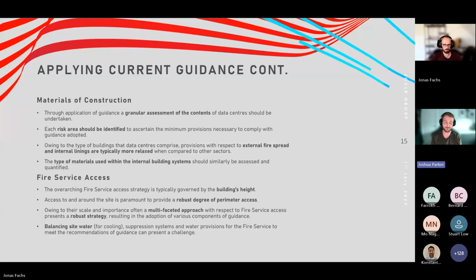Through materials and construction, through application of guidance, we can look on a granular basis and view each individual component of that data center. As we looked through the figure of the internal arrangement of the data centers, they are almost quite cellular in the makeup. Risks are broken down and constricted to the space in which they're located. So we break it down to look at those individual areas and view the risks posed by those areas on an individual basis. How do we apply, how do we select, and propose materials that are suitable for those risks is incredibly important.